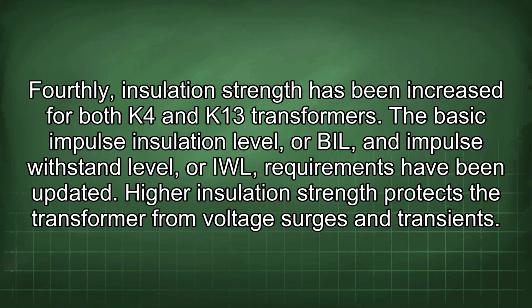Fourthly, insulation strength has been increased for both K4 and K13 transformers. The basic impulse insulation level, or BIL, and impulse withstand level, or IWL, requirements have been updated. Higher insulation strength protects the transformer from voltage surges and transients.